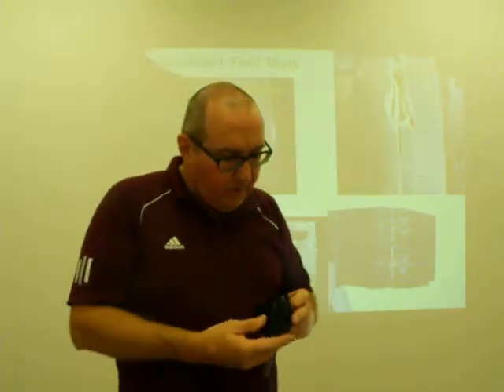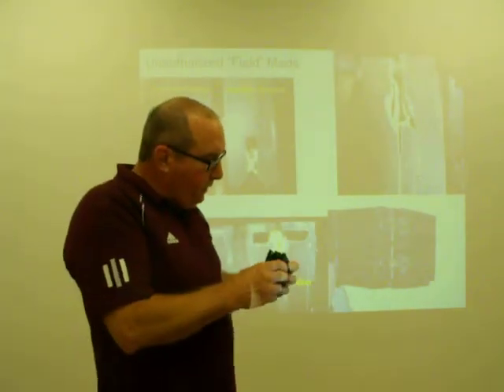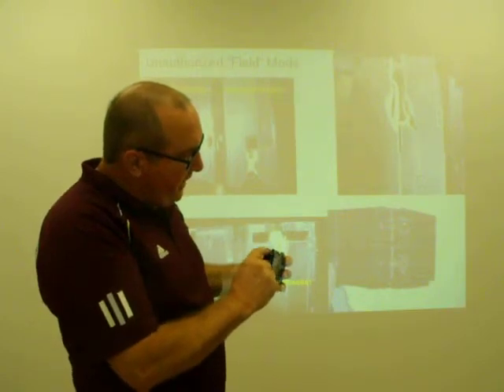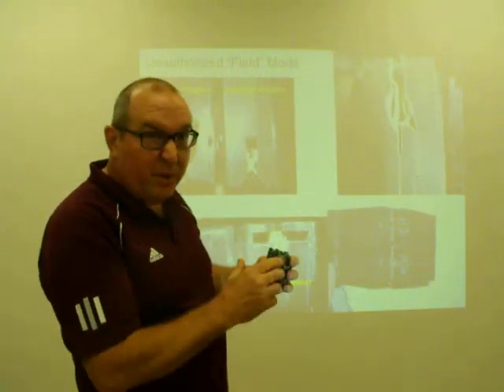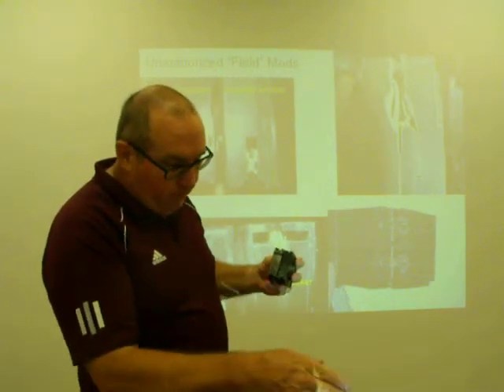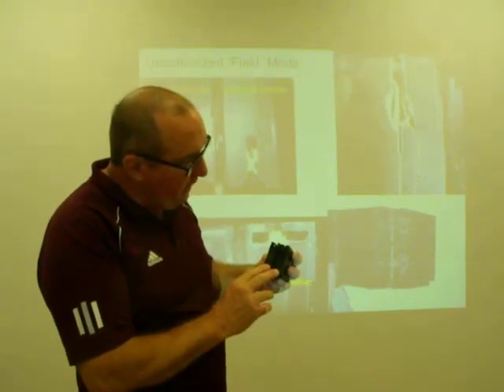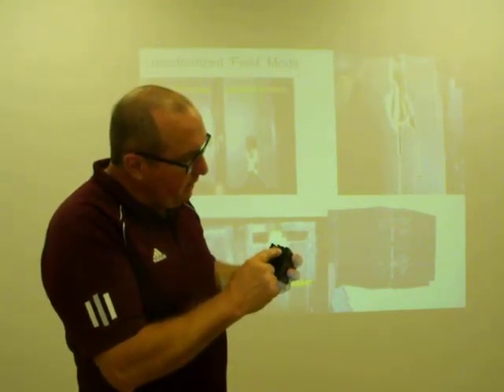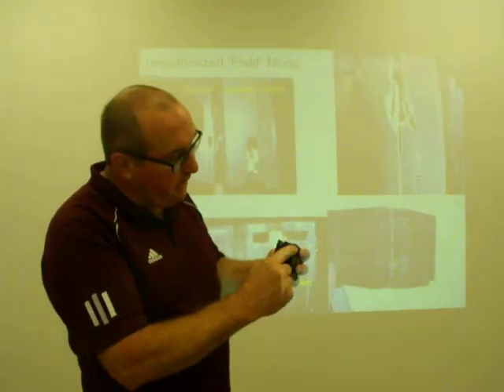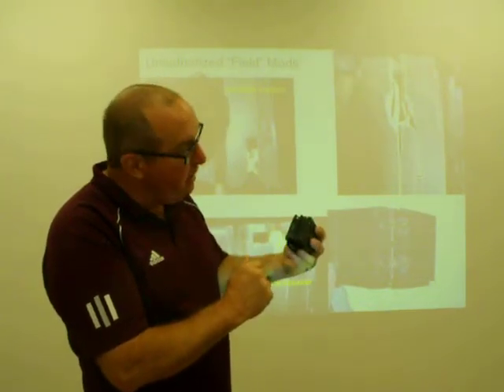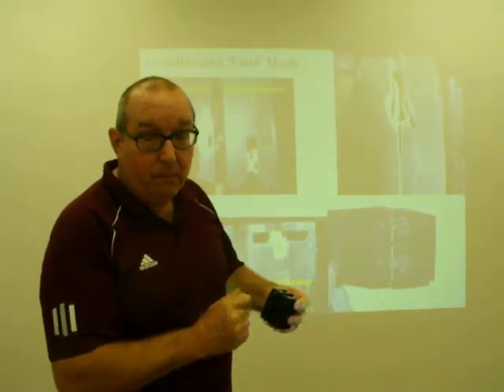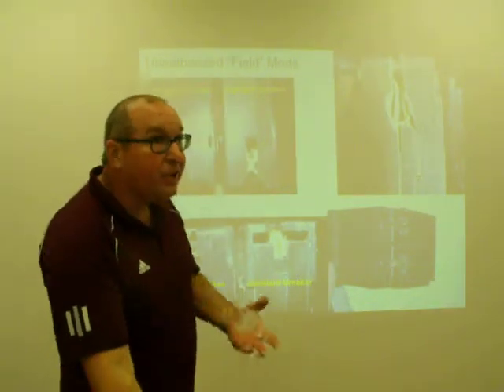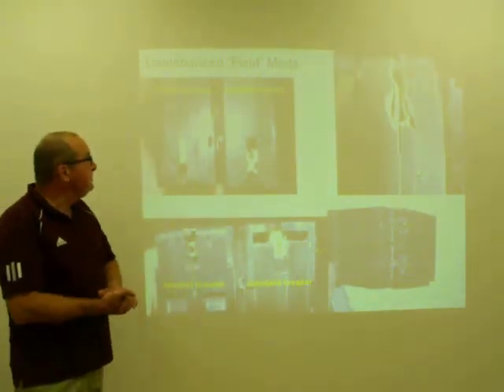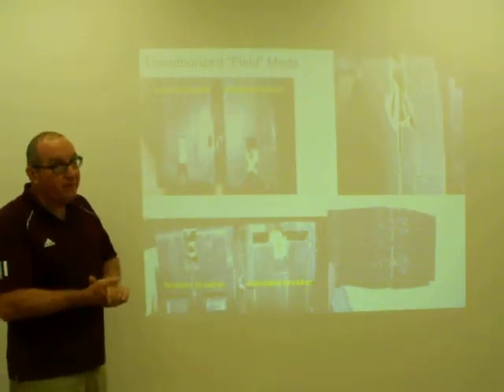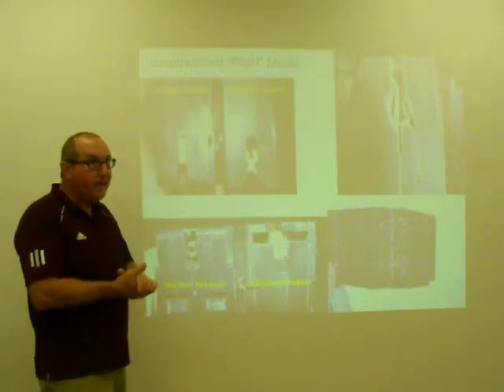Well, I see what the problem is. See, this other breaker has these notches on either side, so it'll slip over those tabs that are parallel to the main bus. All I have to do is take my needle nose pliers or something and chip out the bakelite case here, and I can make that fit. Another violation of the UL listing. No one is authorized to modify the equipment in the field except the manufacturer.